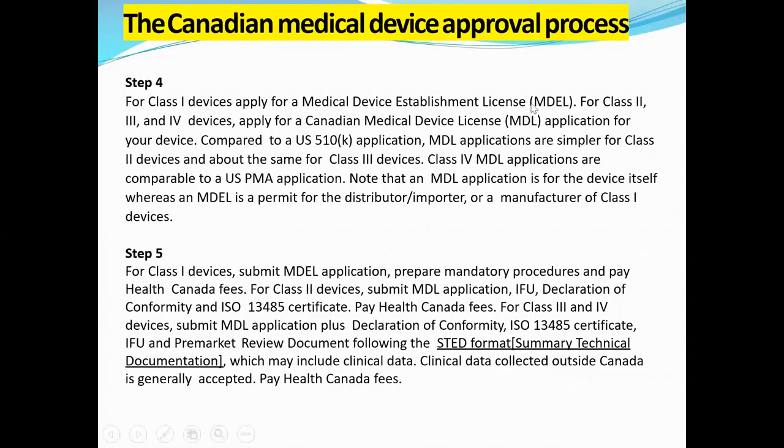So very simple: once you get the license, it is a sort of permit through which you can distribute or import your medical device. And the MDL for class 2 is as good as a US 510(k) application. For class 1, prepare the mandatory procedures, submit the application and pay Health Canada fees, and go ahead.